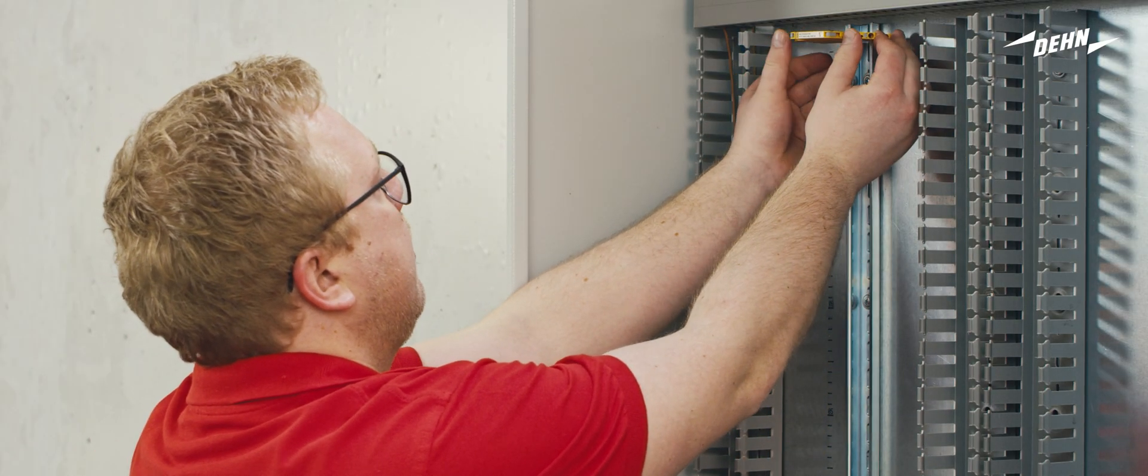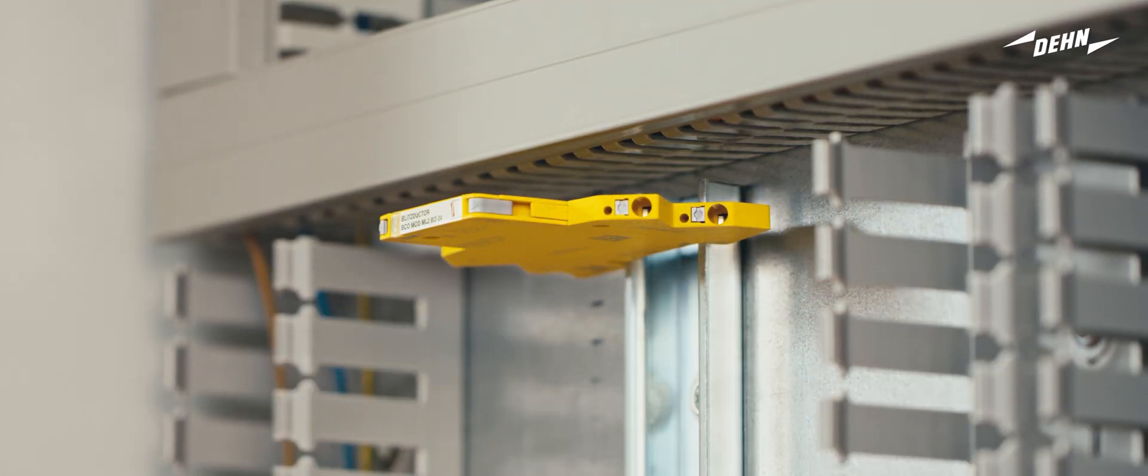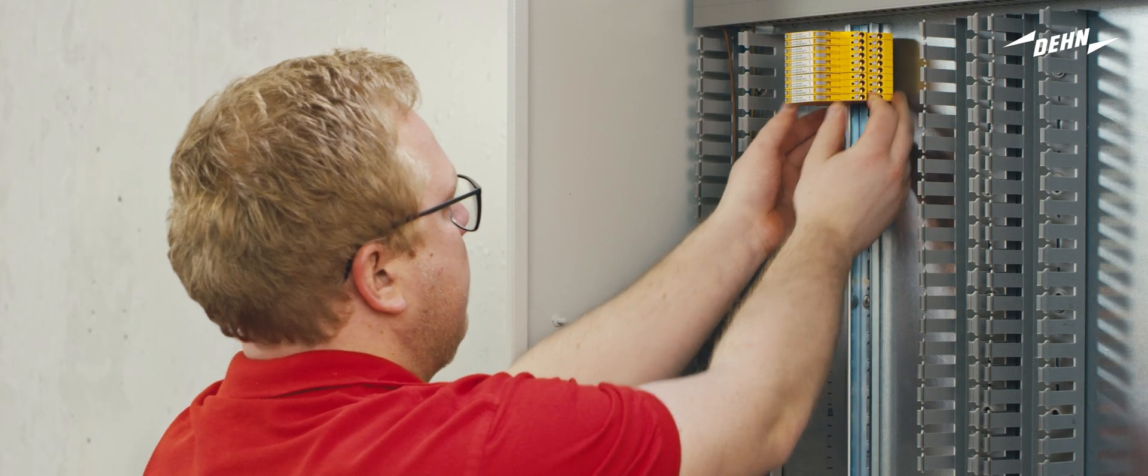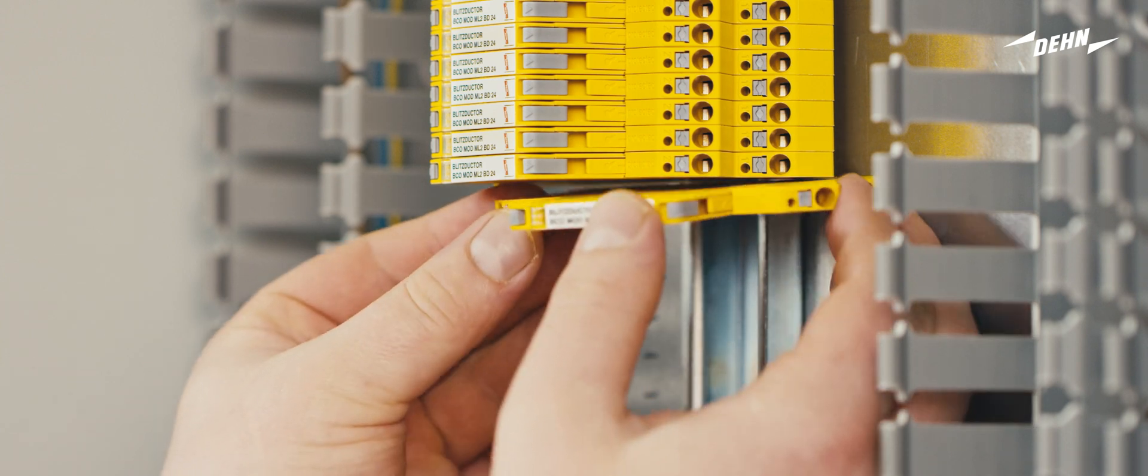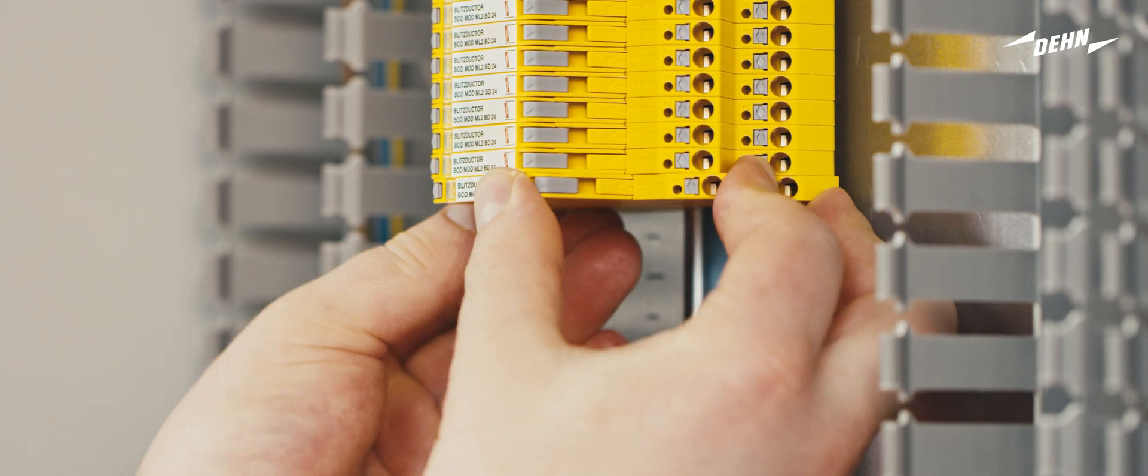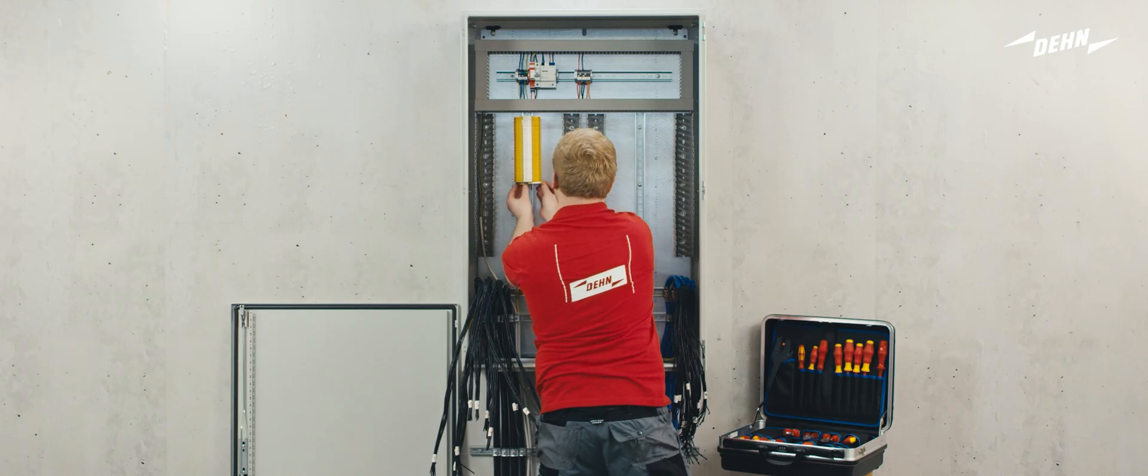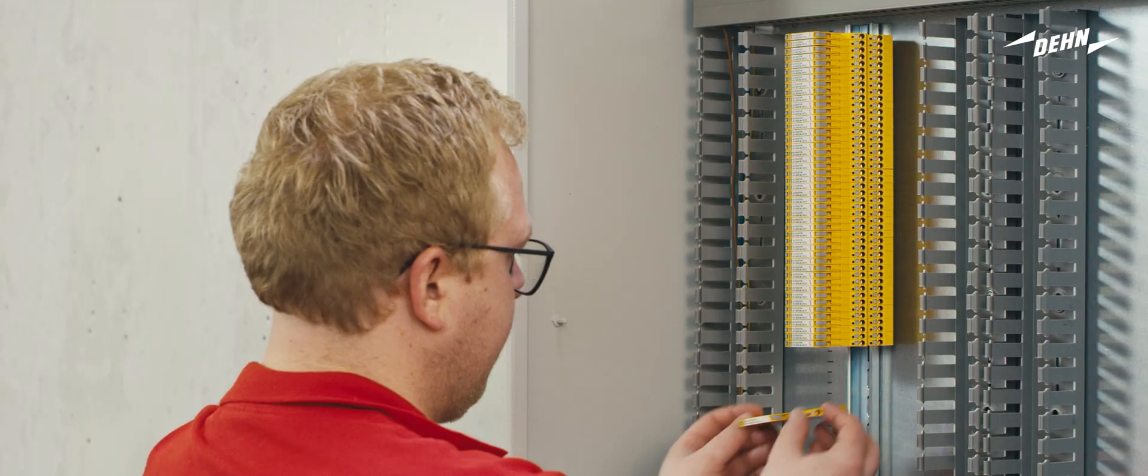Snap the arrestor into the DIN rail. The practical thing here is that the device is automatically earthed by contacting the DIN rail and you don't need to connect a separate earth wire.